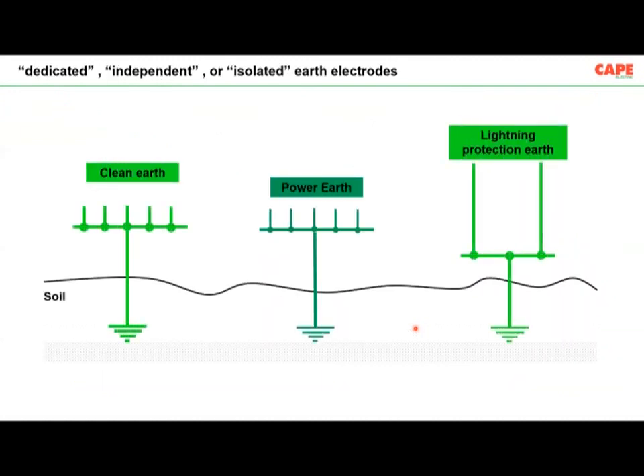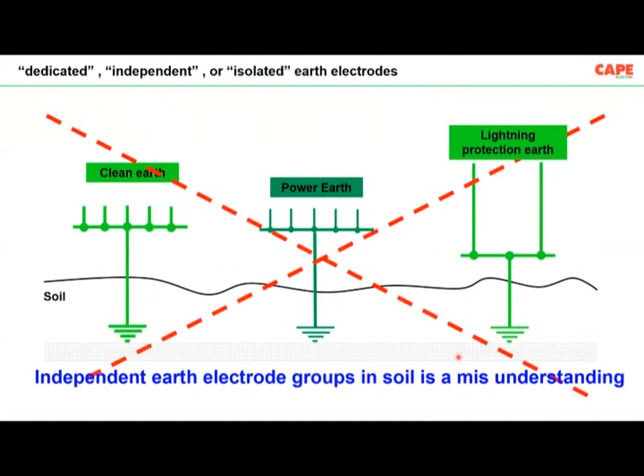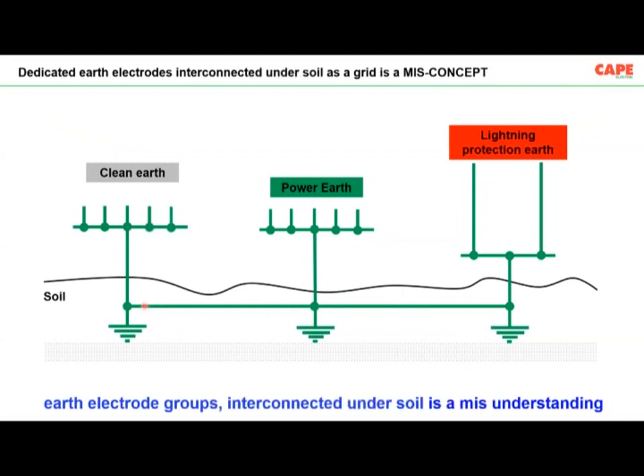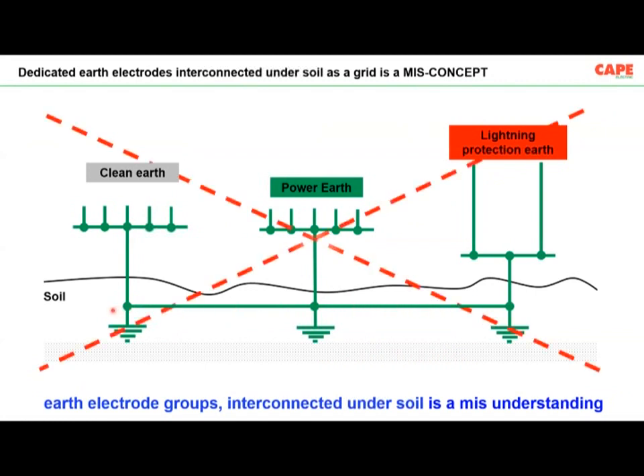Nowadays, we also make earthing in this fashion. A group of earthing interconnected, like electronics interconnected together to one earth pit, the power earth, all the electrical items to one earth electrode, lightning protection to one earth electrode. Unfortunately, this is also wrong. You should not follow this. You will not be able to get safety in this case. And if you have different earthing and you interconnect all the earth electrodes under the soil as a ring or a grid or whatever, this is also wrong. You will not be able to get safety.